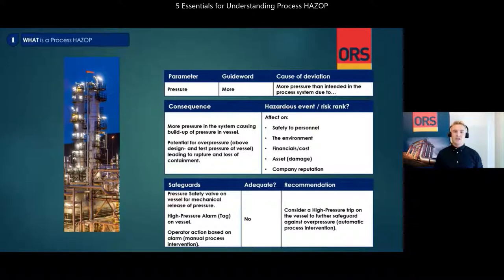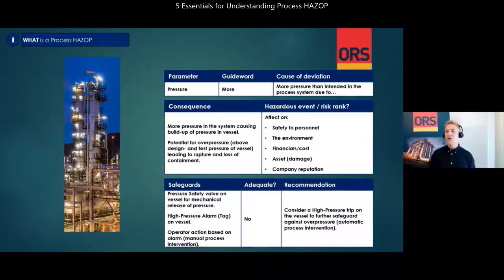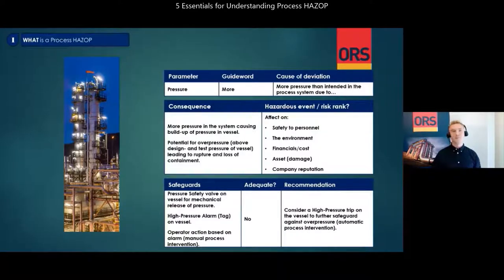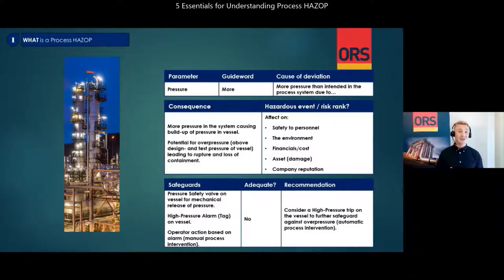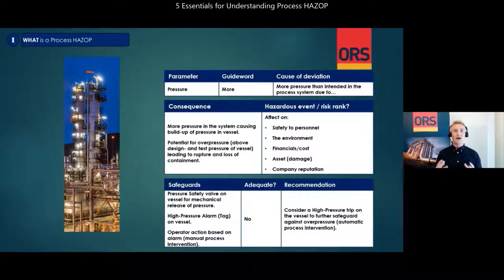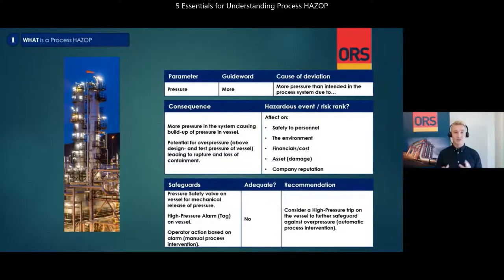If the safeguards in place are deemed insufficient to cater for the event, a recommendation is raised. For example, consider a high pressure trip on the vessel to further safeguard against overpressure — this would then be an automatic process intervention. This was a very high level introduction to the methodology. If you have questions regarding what guide words to use, how to divide the system into nodes, and when and how to apply risk ranking and residual risk ranking, and how to write good recommendations, please write in the comment section during this presentation.